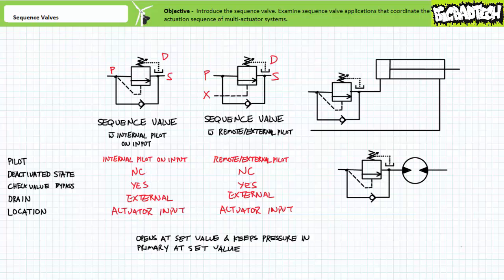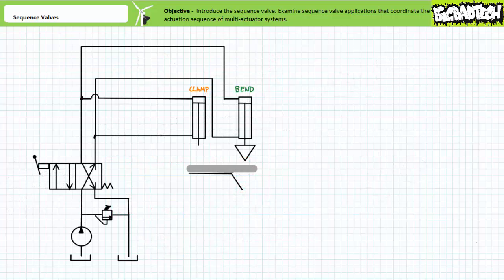We'll discuss kickdown sequence valves in a moment that exhibit slightly different behavior. Note that sequence valves can either be direct or pilot operated, with the understanding that a direct acting sequence valve might be faster acting than a pilot operated sequence valve. However, it may illustrate early creep of the sequenced actuator given direct acting valves tend to exhibit cracking behavior. The classic application example of sequence valves is a clamp and bend circuit operated by a single directional control valve. The desired function is to first clamp and then bend the object, not clamp and bend all at once, or worse yet, bend it then clamp it. A sequence valve can be used to automatically coordinate this desired actuation sequence.